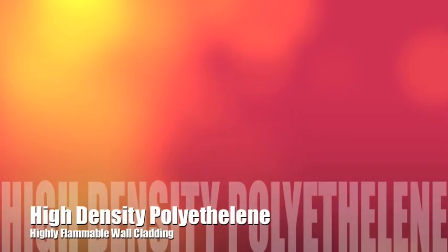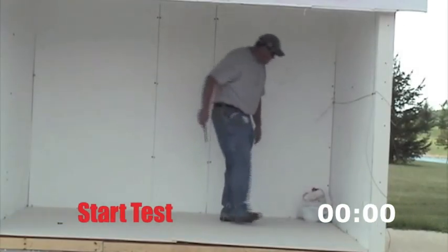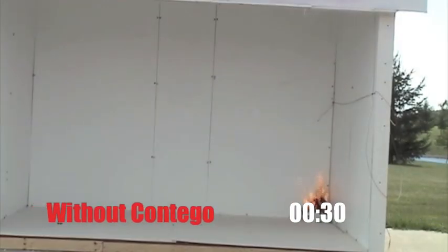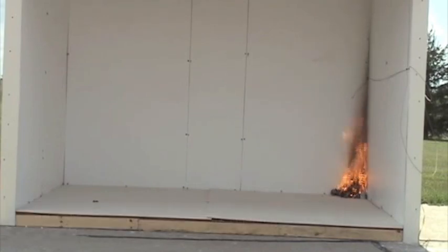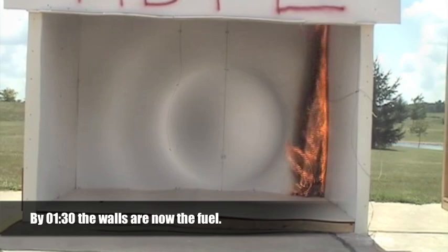We'll start with HDPE wall panels — widely used, but highly flammable. HDPE is short for high-density polyethylene. Technicians from Grinnell start with a small fuel load in a room without Contego's protective fire barrier latex. Well, in less than a minute, the walls are catching, and 30 seconds later, the wall panels are now the fuel.